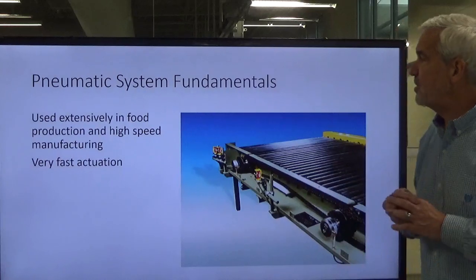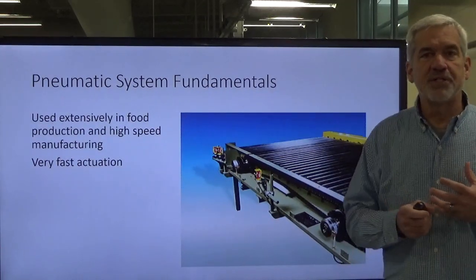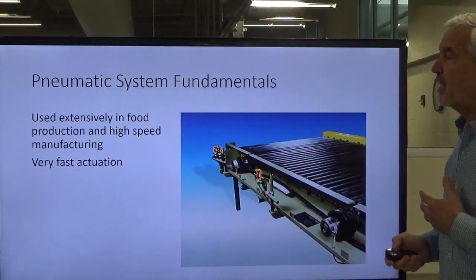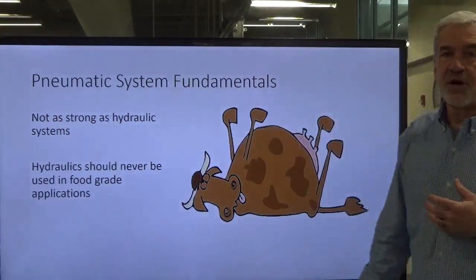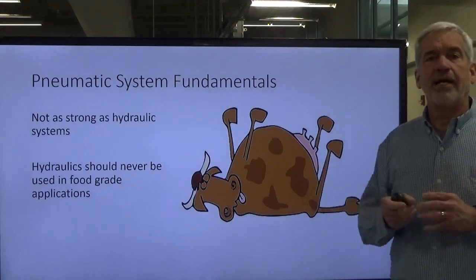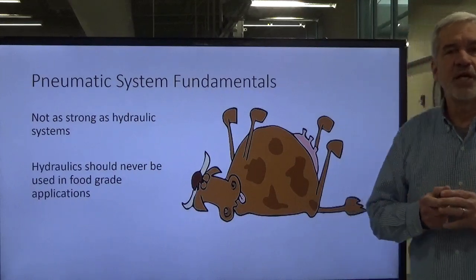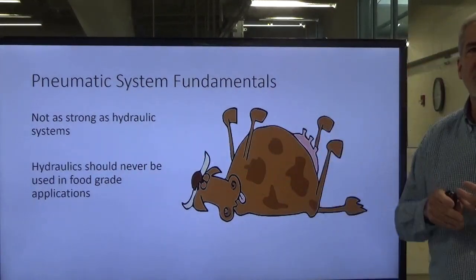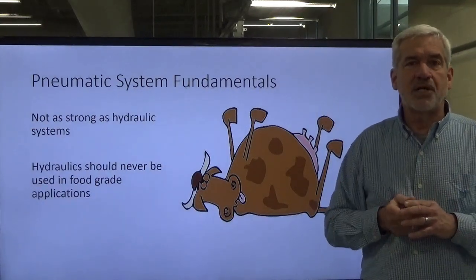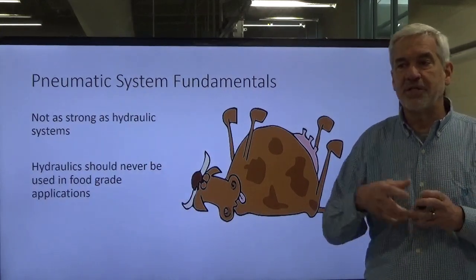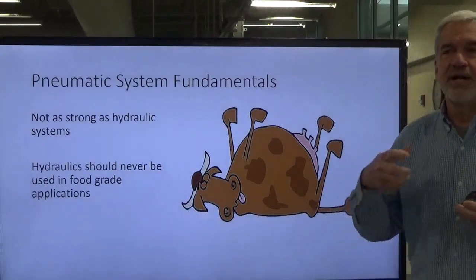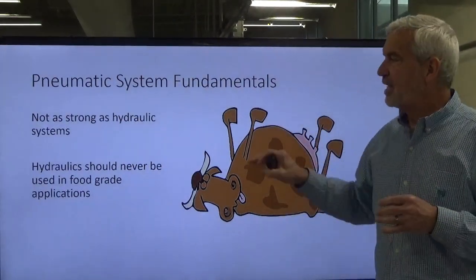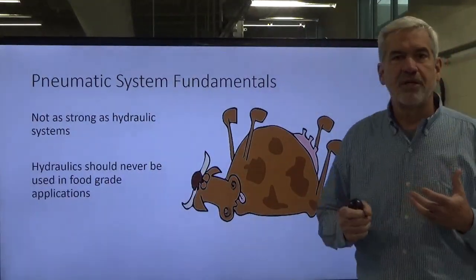Pneumatics are used extensively in the food processing industry. They have very fast actuation — cylinders move much quicker than with hydraulics. One drawback is they're not as strong as hydraulics. Hydraulics should never be used anywhere food is involved; a hydraulic leak into feed or beer could contaminate it, harm animals or people, and create serious liability. I used to work in a feed mill as a maintenance supervisor, and we used pneumatics exclusively for that reason. You certainly don't want hydraulic fluid in your beer.